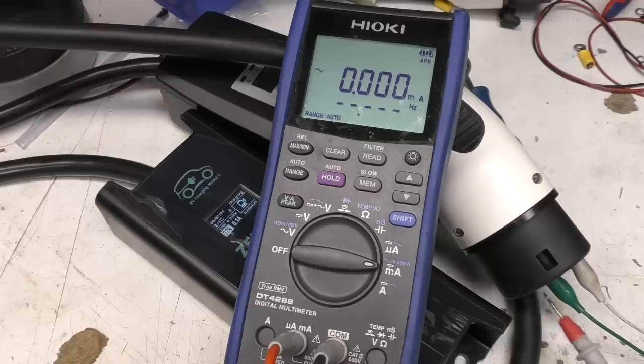It trips, but as soon as you disconnect the car, it will latch so that, you know, if you come back to the car it will be tripped and not charging. But the car might detect the fact the power's gone, and you could get some sort of cycling. So this is slightly less good in that it doesn't latch until you power cycle to reset that fault condition.